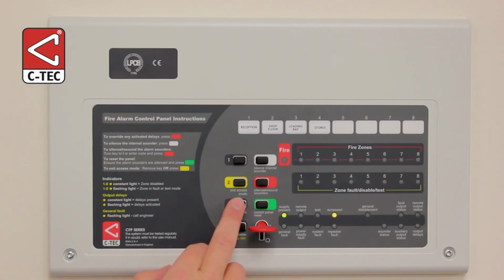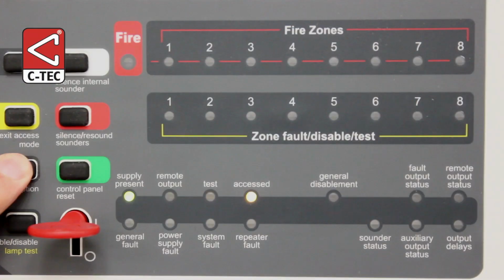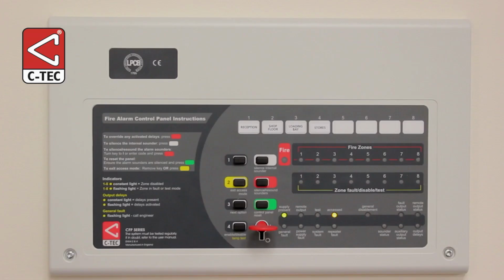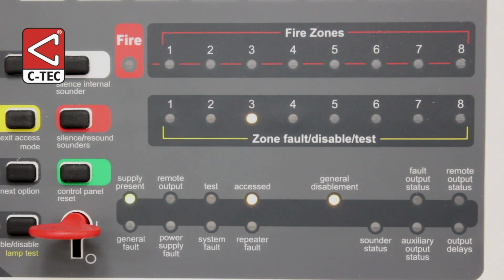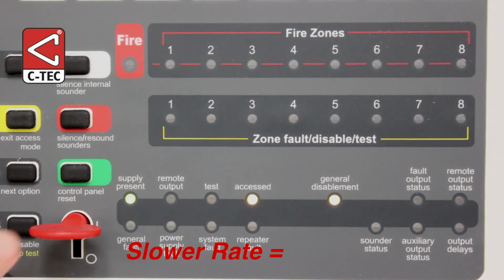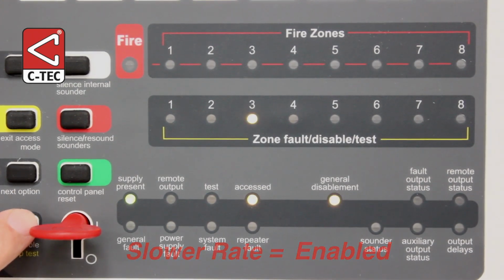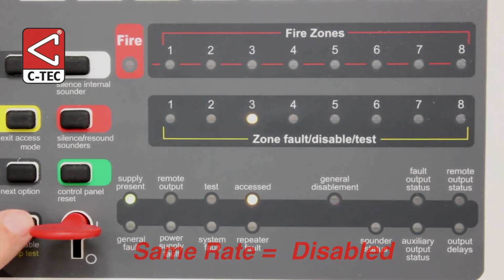To start the process, press and hold the Next Option button for 3 seconds until the general disablement and Zone 1 fault lights are flashing yellow. For the purpose of this video, we'll use Zone 3 as an example of a zone that needs disabling. Press the Next Option button until Zone 3 is flashing. If it flashes slower than the general disablement light, its current status is enabled. If it flashes at the same rate, its status is disabled.